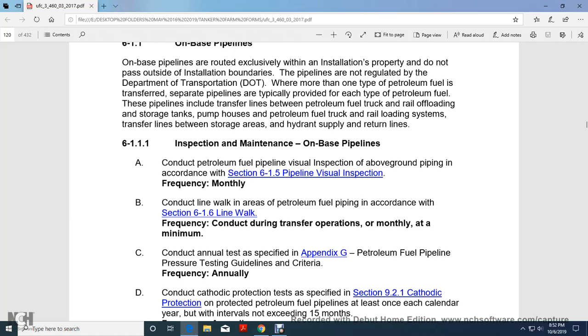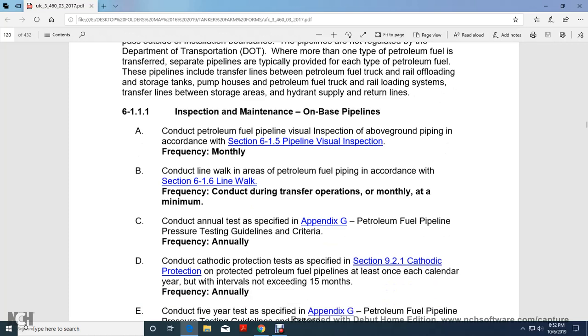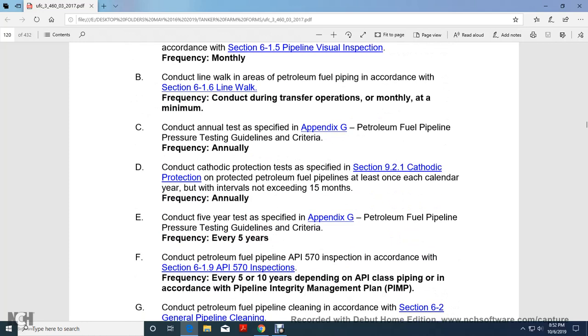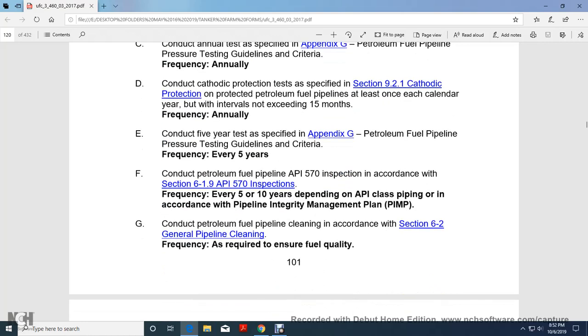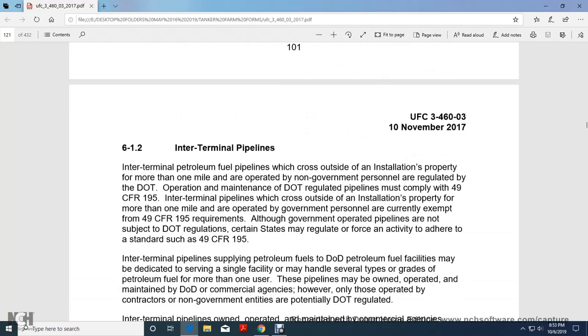C. Conduct annual testing as specified in Appendix G, petroleum fuel pipeline pressure testing guideline criteria. D. Conduct cathodic protection testing as specified in Section 9.2.1 on cathodic protection of the petroleum fuel pipelines at least once each calendar year, but with intervals not exceeding 15 months. Conduct five-year tests as specified in Appendix G, petroleum fuel pipeline pressure testing guidelines criteria, frequency every 5 years. Conduct a petroleum fuel pipeline American Petroleum Institute 570 inspection in accordance with 6-1.9 API 570 inspection, frequency every 5 to 10 years depending on API class of piping, in accordance with the Pipe Integrity Management Plan, or PIMP. Conduct petroleum fuel pipeline cleaning in accordance with 6.2 general pipeline cleaning, as frequently as required to ensure fuel quality.